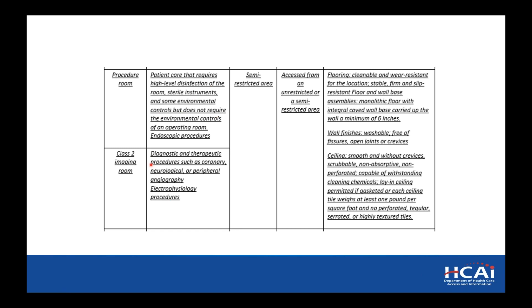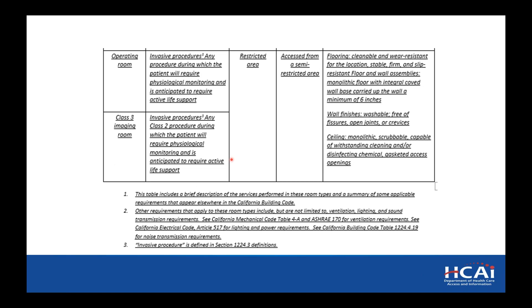Okay, so the big deal here for us is adding this procedure room and class 2 imaging room. If you have an existing diagnostic room that has migrated or is being converted into a class 2 imaging room, it can remain in the imaging department and be accessed from an unrestricted corridor, but the room itself would need to be semi-restricted. Again, our staff do not make the determination if your procedures meet the requirement of a class 2 imaging room or a class 3 imaging room, but it should be identified in the functional program, and it will be submitted to CDPH to make that determination.